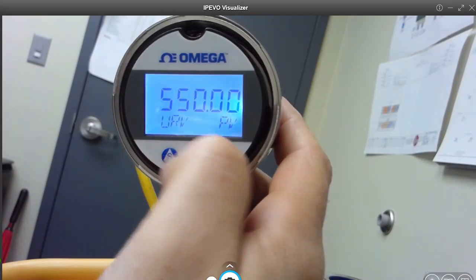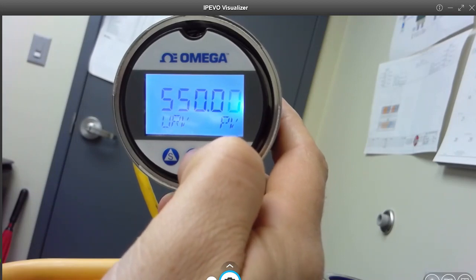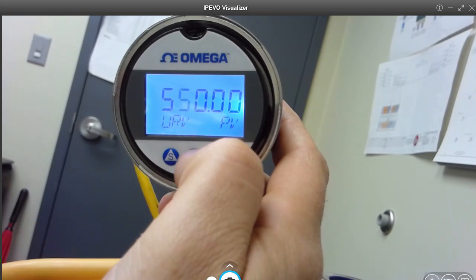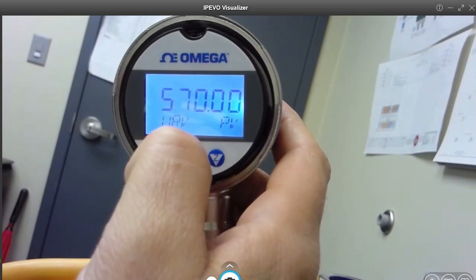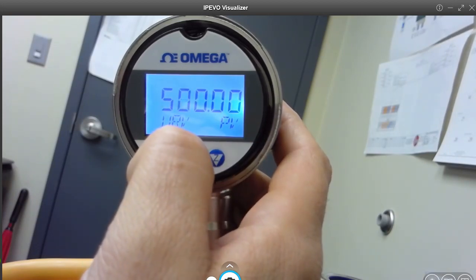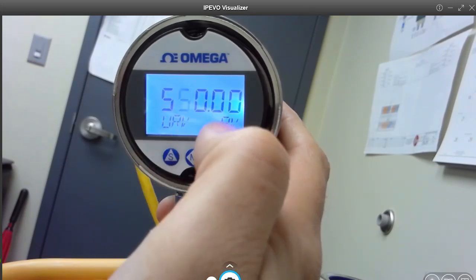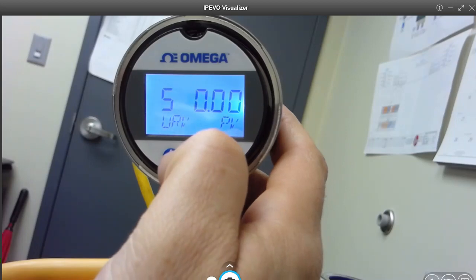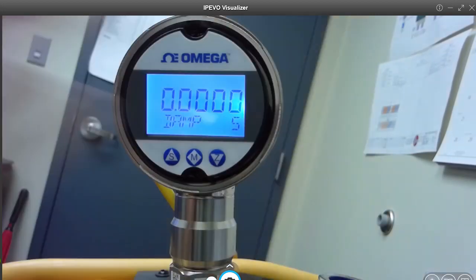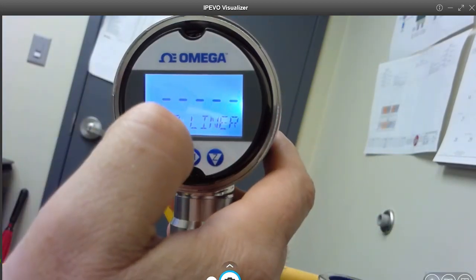There's our low process. Here's our upper. Now you can see how we can move our decimal point. Remember, don't hit the menu key, that saves. You can only go up. So if I want to scroll up and say 590, I'm going to keep scrolling all the way back to 550. And then once I have 550 PSI, I'll hit the menu key. Dampening, we don't care about. We want to hit the menu button and verify that our milliamp is linear, so our signal will be linear based on the pressure.